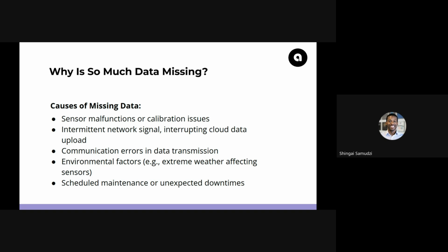And again, some of them, the way that they configure the data upload, if there is a period of time where you're not able to upload, they may not properly timestamp the data. So yes, they are storing the data, but you may end up with data at noon, then a 5-hour gap because the internet signal is down, and then at 5 p.m. a massive spike, a massive data upload where all the missing data between noon and 5 p.m. was aggregated and sent all at once. So you have this wide range of different approaches that OEMs take to managing intermittent network signal. And all that means is that you end up with a very messy or patchy data set at the very end in your cloud upload.